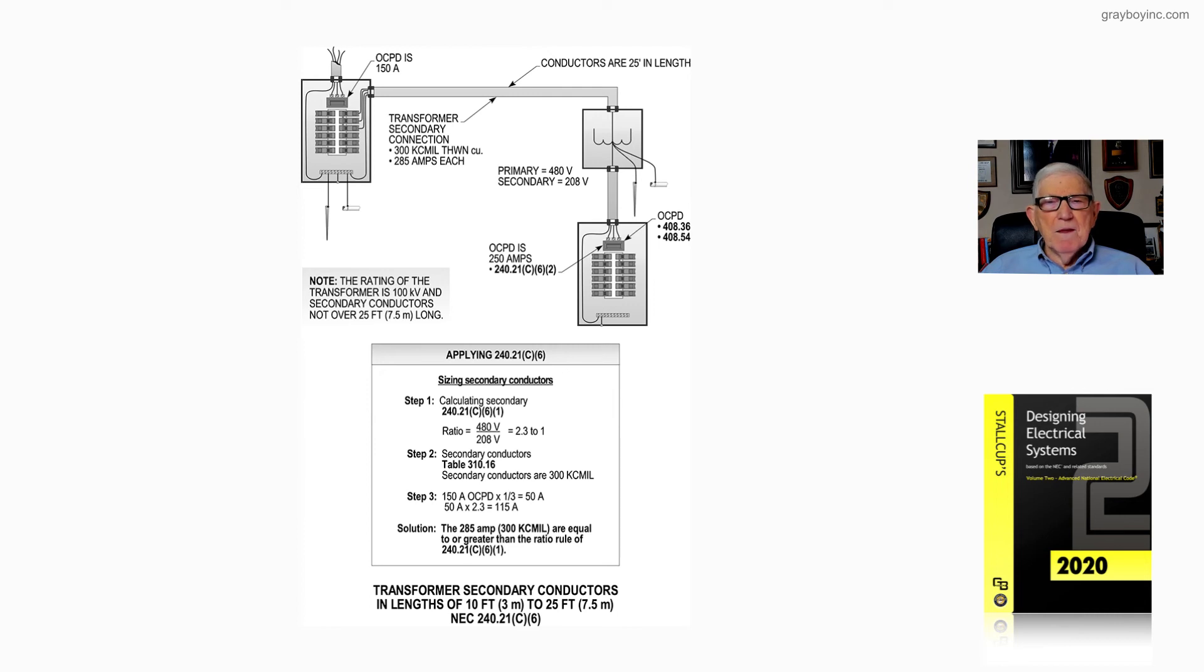So this illustration 20-39 is illustrating the procedure when you're applying 240.21C6 for a commercial tap and not 240.21C3 for an industrial tap. So you folks installing these separately derived systems, you want to know the difference in the 240.21C3 industrial tap and how that would be applied in a calculation.